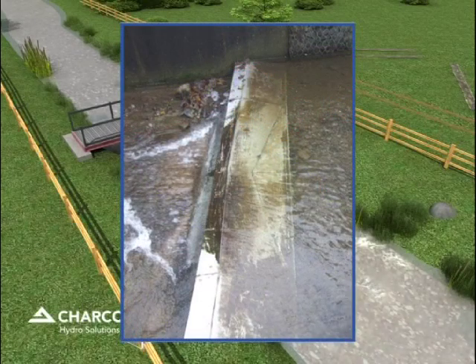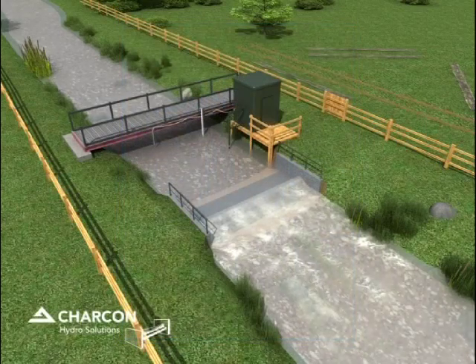For conditions of fast-flowing heavy debris, steel plating can be fitted pre-installation to prevent excessive erosion. Depending on site conditions, the weir will remain at supercritical flows at all ranges. The weir is also used where downstream controls are critical at extreme high flows, even though the low-profile structure is effectively submerged.